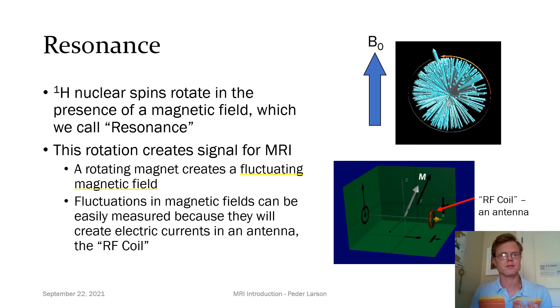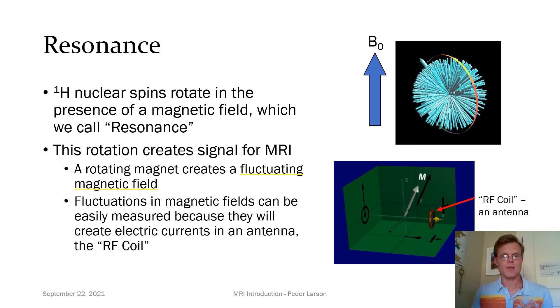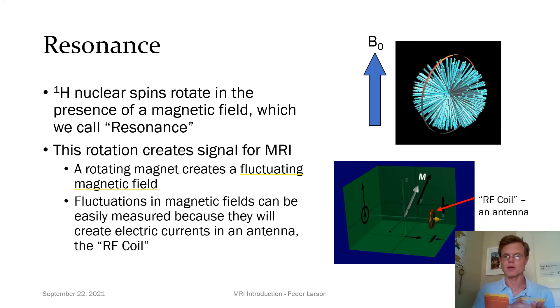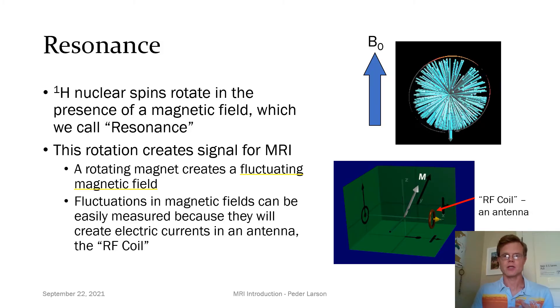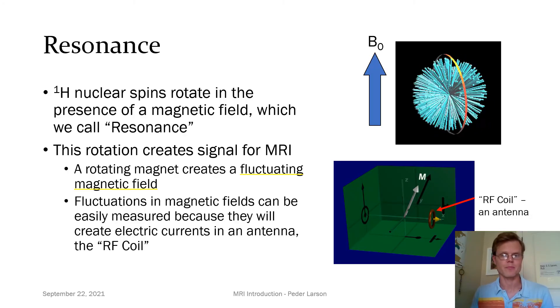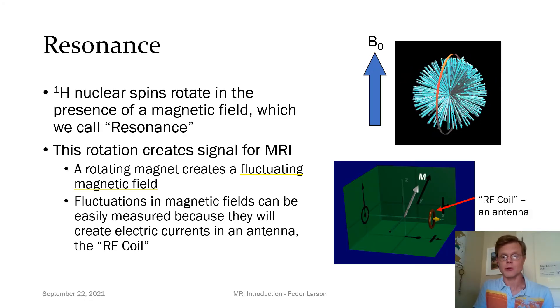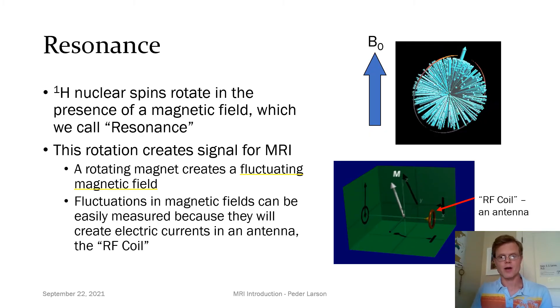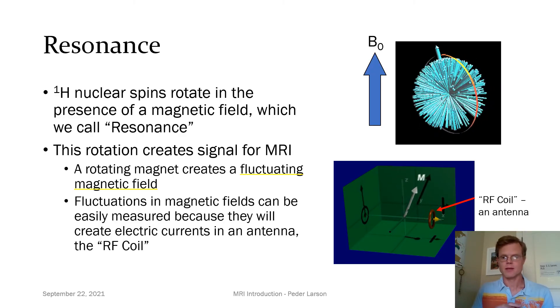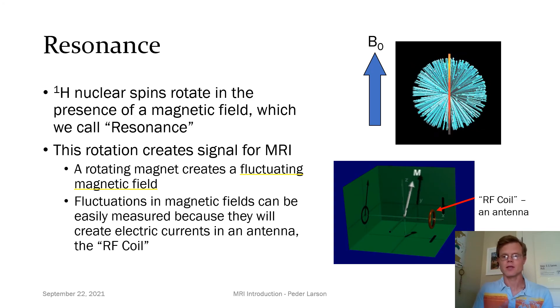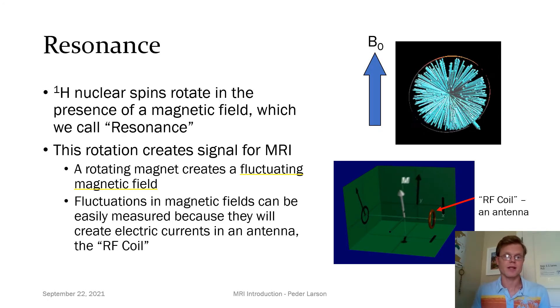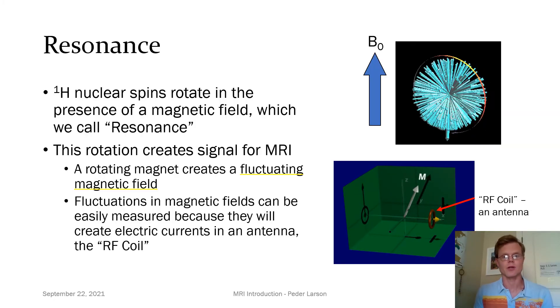The next part of MRI is magnetic resonance. What does resonance mean? The resonance phenomenon is this process where the hydrogen nuclear spins are going to rotate in the presence of a magnetic field, illustrated in the top right plot where each small turquoise arrow represents a nuclear spin rotating around the direction of the external magnetic field. And it is this rotation that actually creates our signal in MRI. This is illustrated in the bottom right diagram, where the white arrow with M represents a rotating magnet, and this creates a fluctuating magnetic field indicated by the yellow arrow inside of the circle. It turns out fluctuations in magnetic fields are very easy to measure — they will create electric currents in an antenna, and what we call the antenna in MRI is an RF coil.